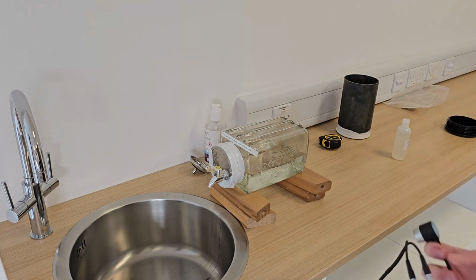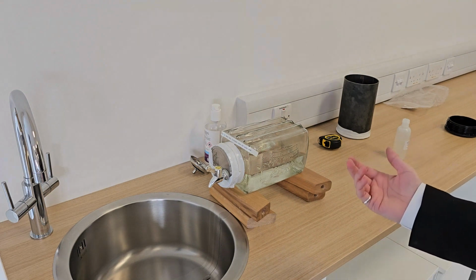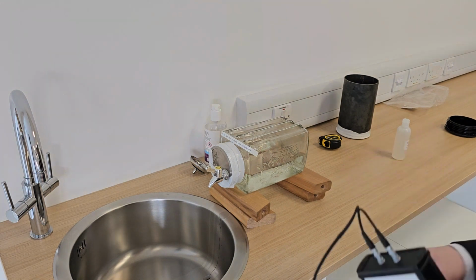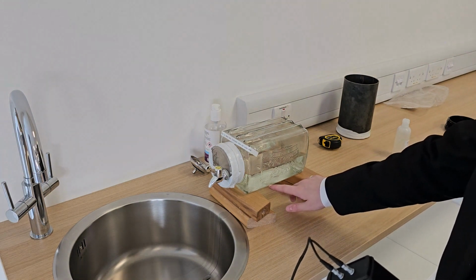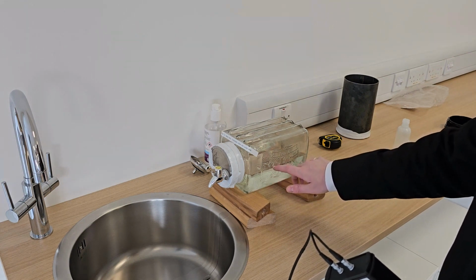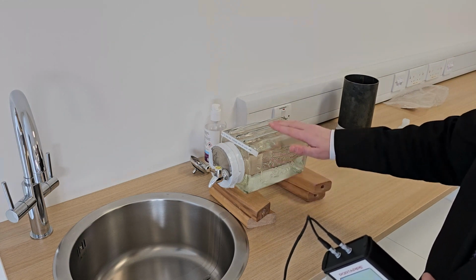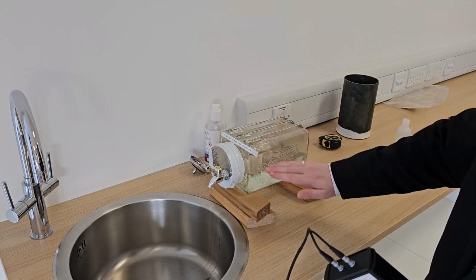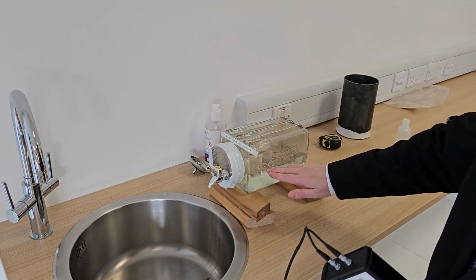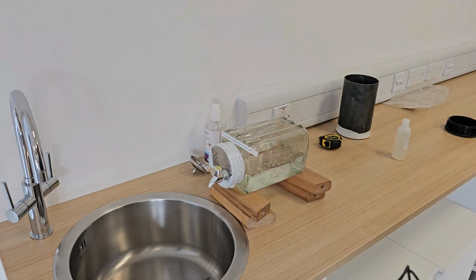For horizontal pipe measurements, we need access to the bottom of the container because the Portapipe is going to transmit an ultrasonic signal through the walls of the container, through the liquid, and that will reflect off either the opposite wall of the container or the surface of the liquid itself. We can use that to determine how much liquid is in the container.